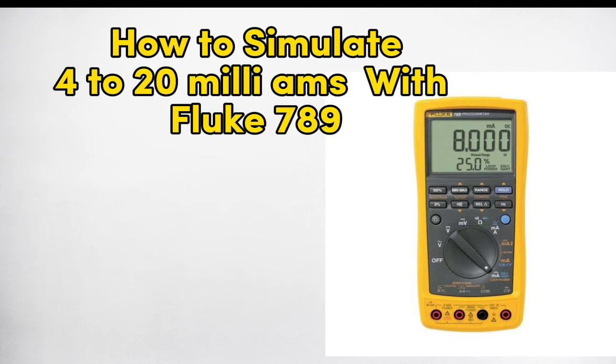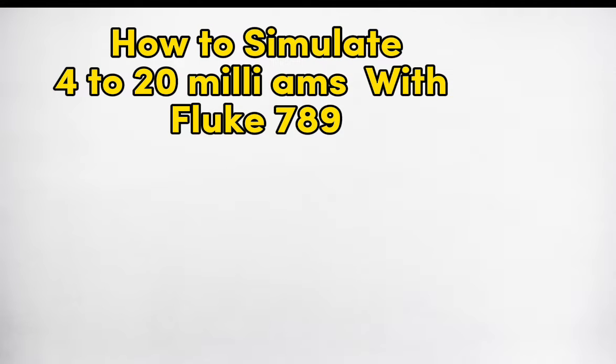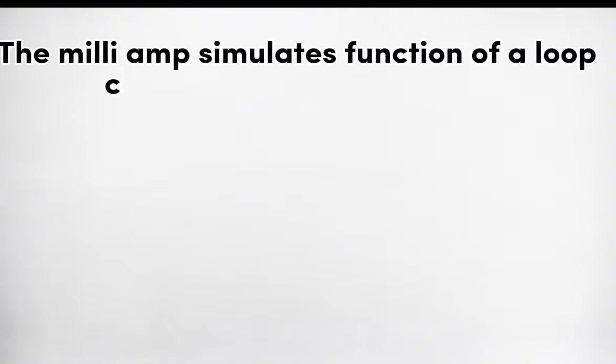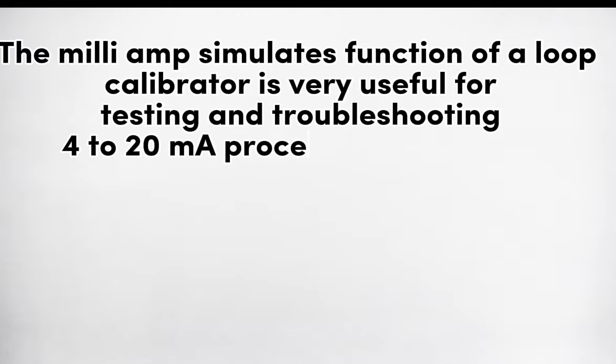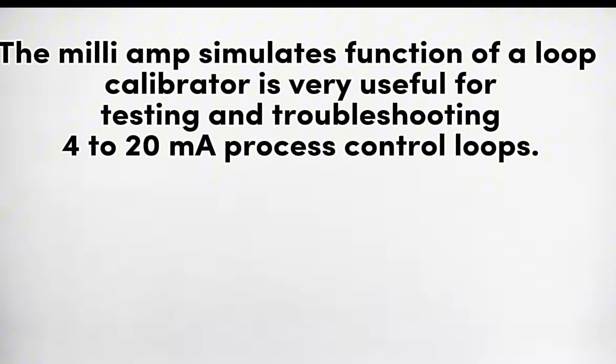How to simulate 4 to 20 milliamps with the Fluke 789. The milliamp simulate function of a loop calibrator is very useful for testing and troubleshooting 4 to 20 milliamp process control loops.